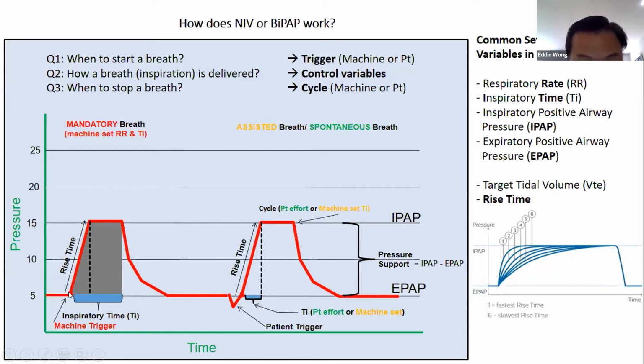And from the time the pressure rises, the inspiration starting, until the time the expiration ends before the next breath starts, this breath time is 6 seconds. Okay, so you have 2 seconds inhale, 4 seconds exhale, and this 2 plus 4 is 6 seconds, 1 breath. Why 6 seconds? Because your respiratory rate is 10. So 10 breaths per minute, 1 minute is 60 seconds, 60 seconds divided by 10 breaths per minute setting. So it becomes 6 seconds, 1 breath.